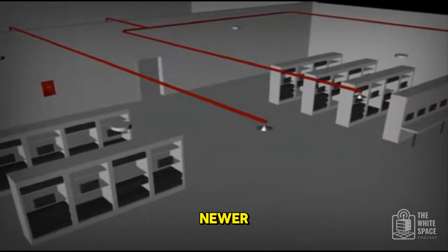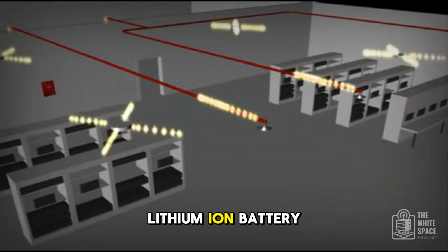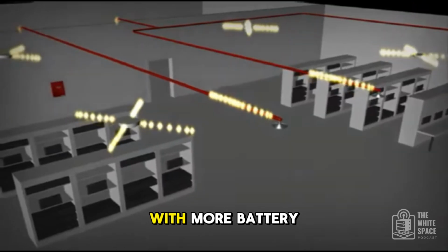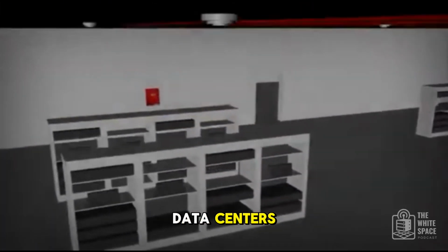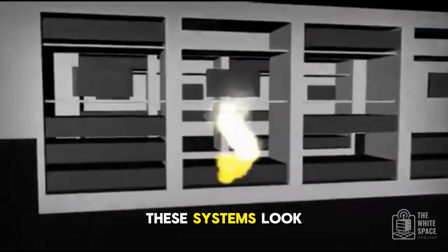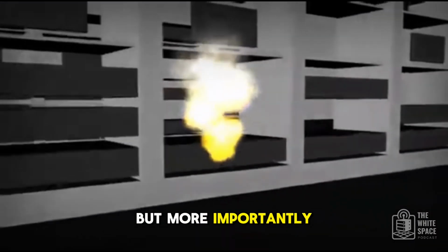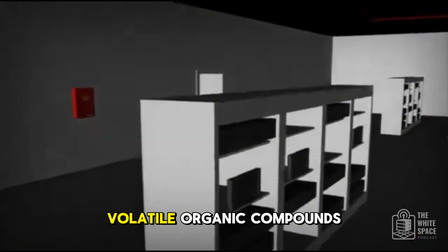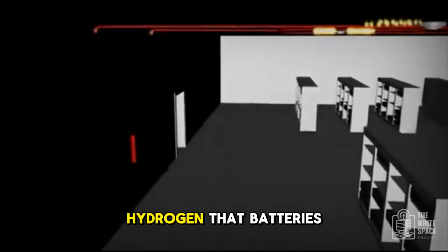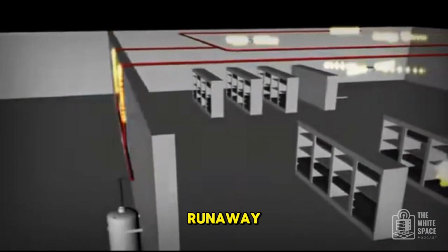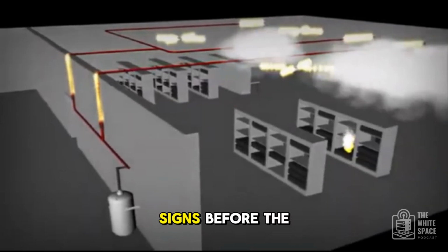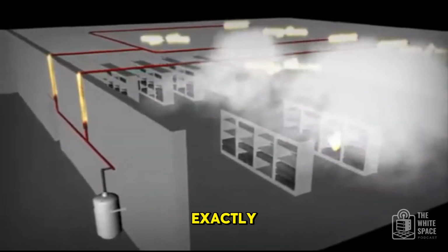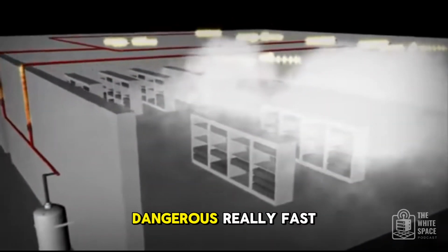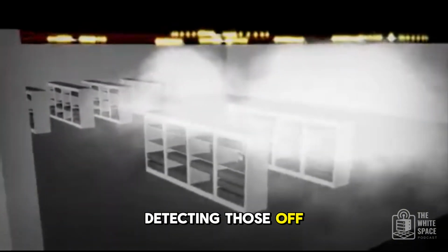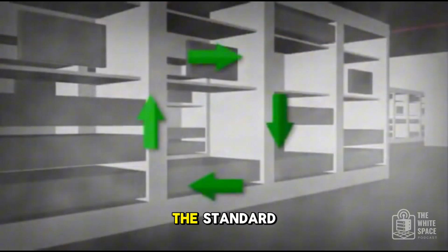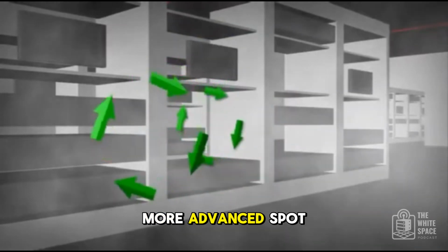Okay. And a newer, important category is lithium-ion battery anomaly detection. With more battery backup systems in data centers, this is critical. These systems look for external stress, but more importantly, they detect specific gases, volatile organic compounds, hydrogen that batteries release before they go into thermal runaway. Ah, so it's detecting the warning signs before the battery catches fire. Exactly. Stage 2 thermal runaway is where it gets really dangerous, really fast. Detecting those off gases is key. Okay, that covers the standard or maybe slightly more advanced spot detectors.